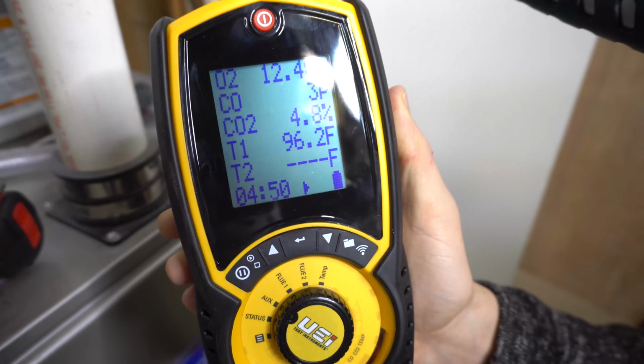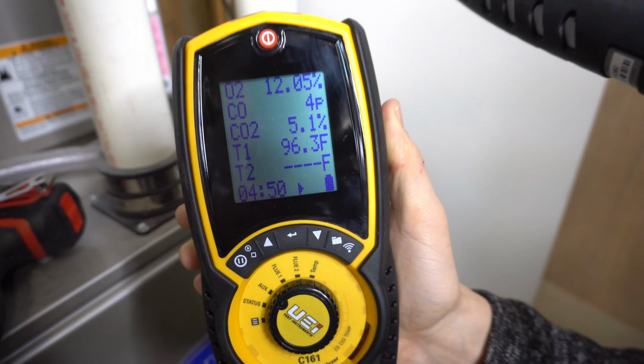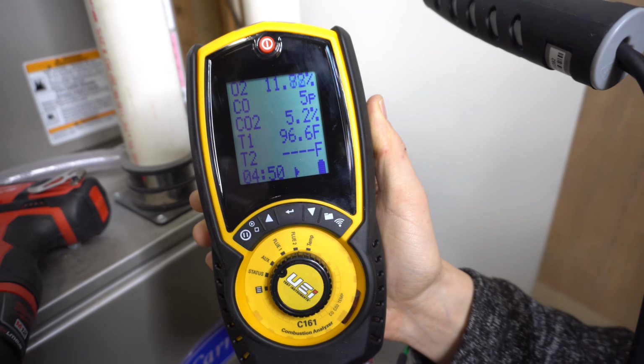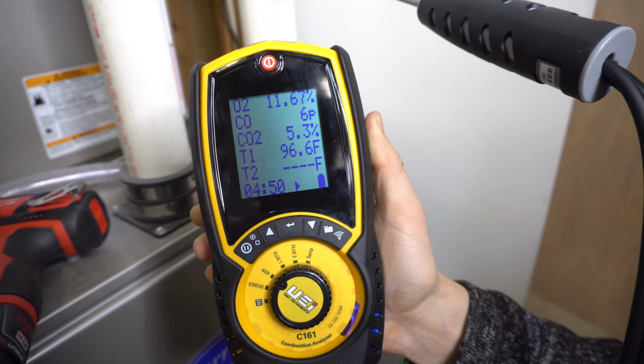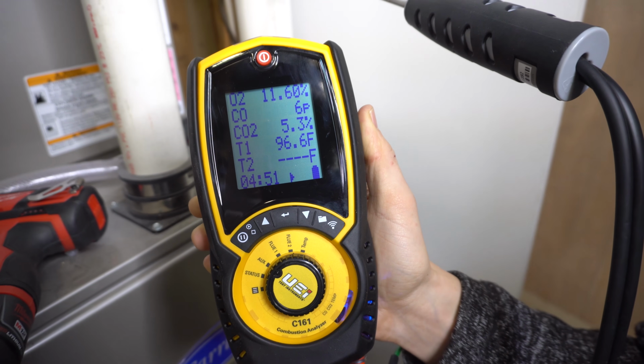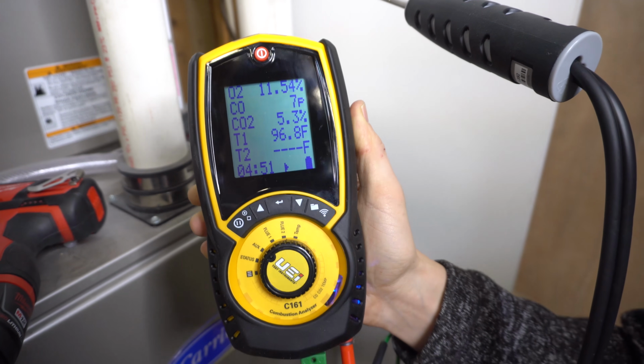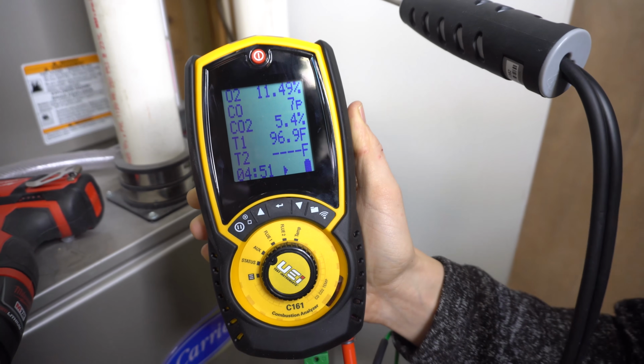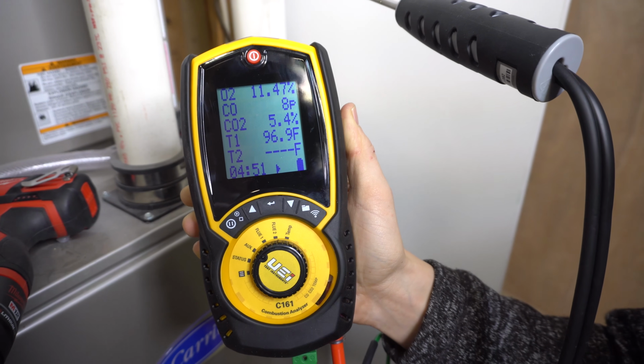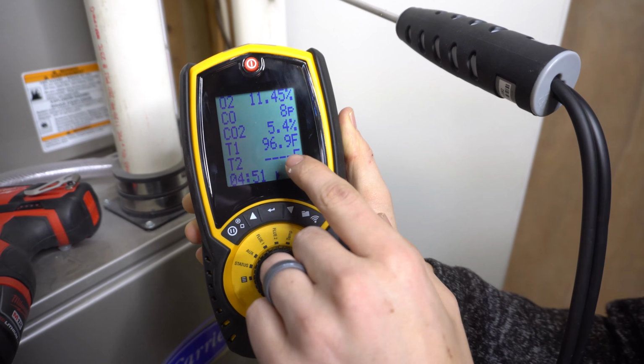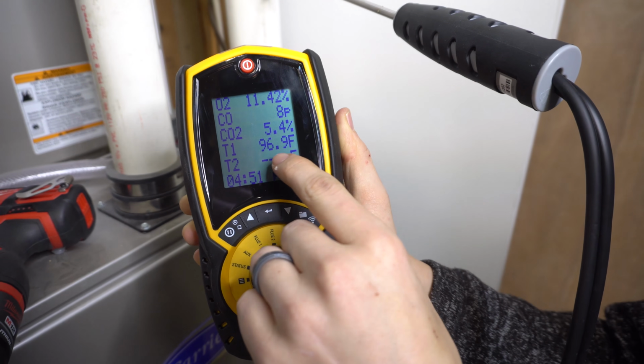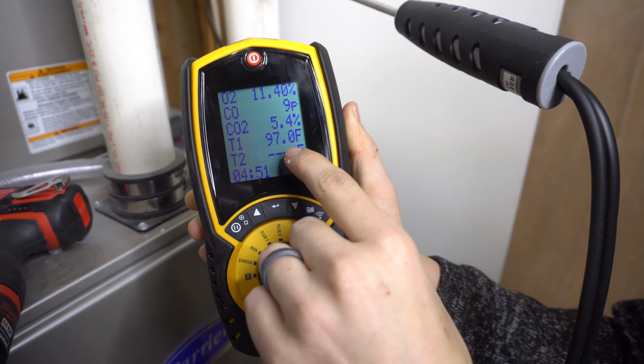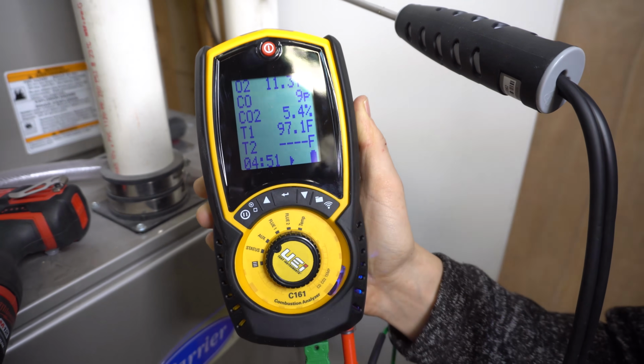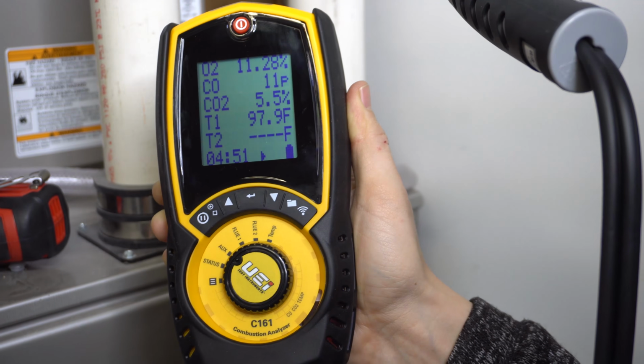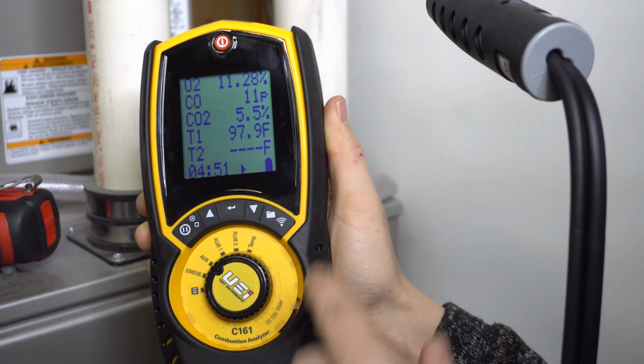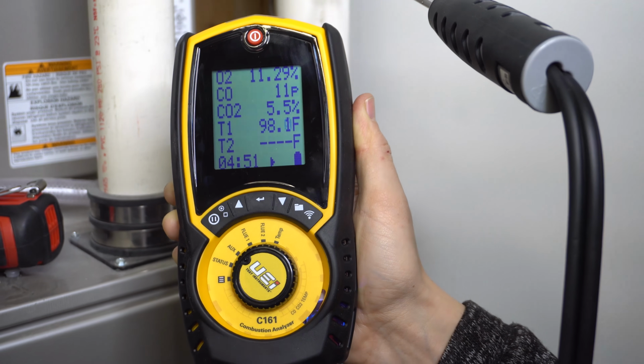As you can see, the oxygen percentage is dropping pretty quickly, whereas the carbon monoxide is going up pretty slowly. So not a lot of carbon monoxide is being pumped out by this furnace. The carbon dioxide is about 5.4. I'm sure that'll change a little bit. Also, the temperature of the flue gases in a high efficiency furnace is much lower than that of a standard 80% efficient furnace. I'll give it a couple of minutes to completely stabilize so we can see what our final numbers are for the low stage.